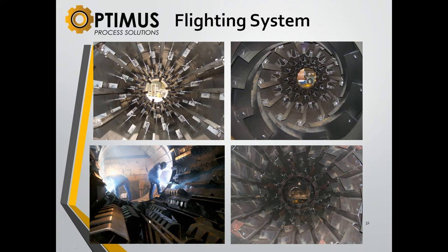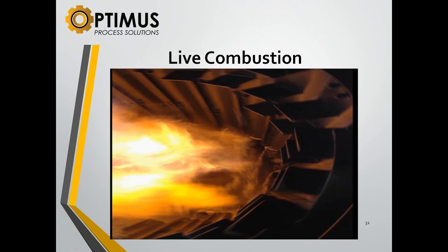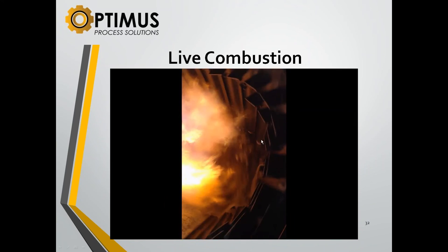So this is a spiral flight right here to push material in before it starts working through the process. And this is just a material flighting section that picks up the material that's already fluffy and ready to veil. Just the shape of the flights has a very different effect inside. You'll see sawtooth flights right here that start to release early and hold product over, and they're used in conjunction with, like, right there, a J flight and 45s. We mix those flights up to attempt to get a constant veil through both the ascending and the descending rotation of the dryer.